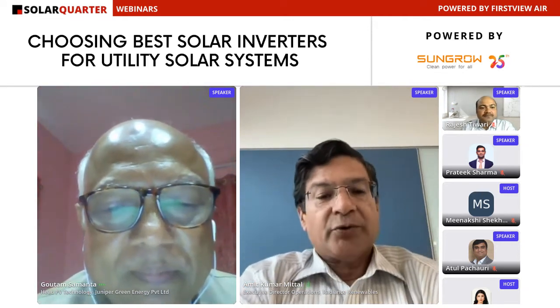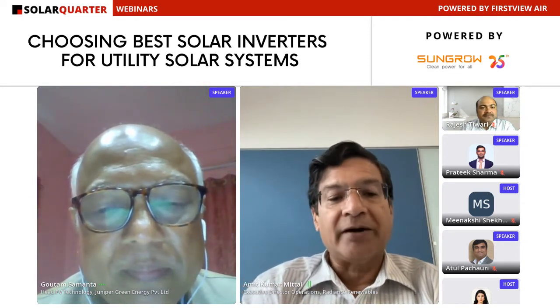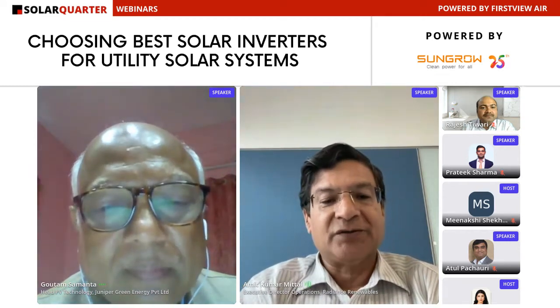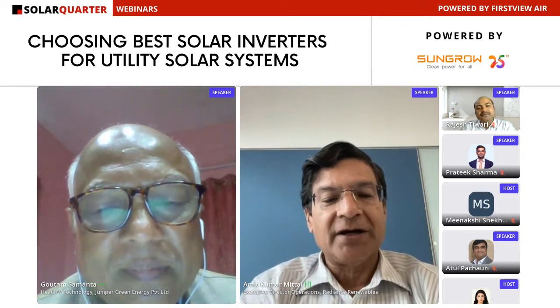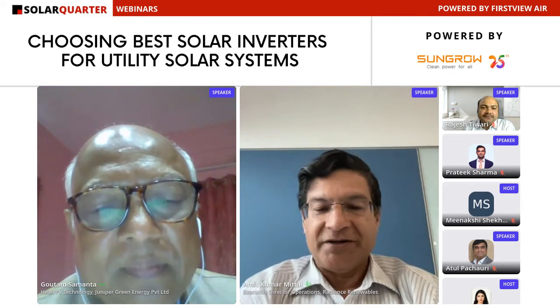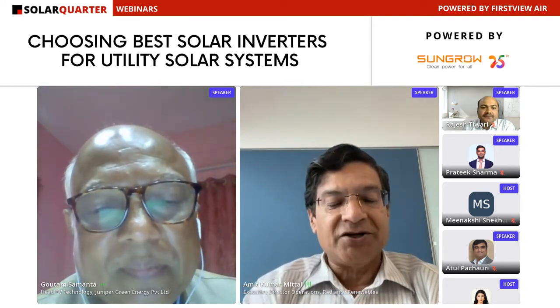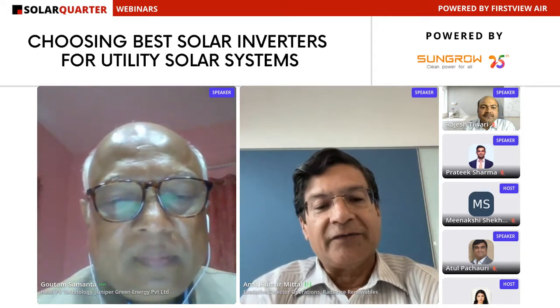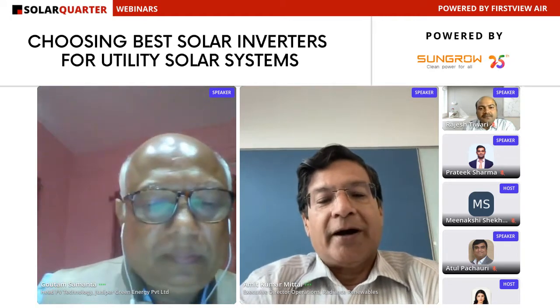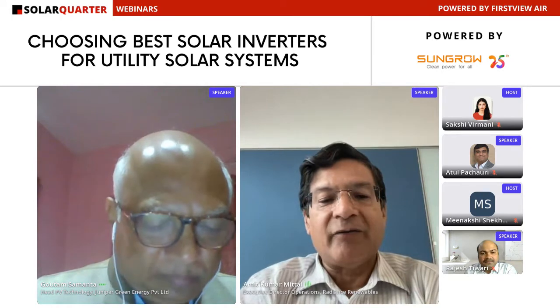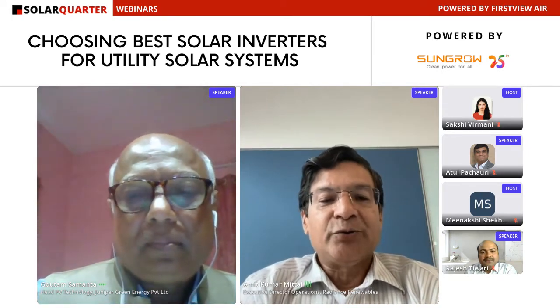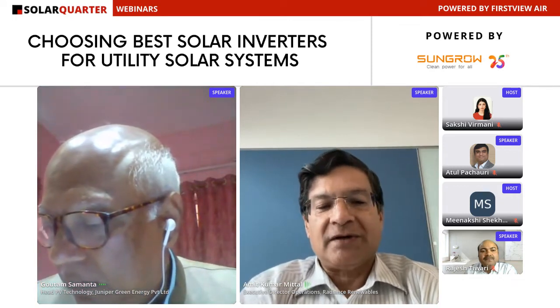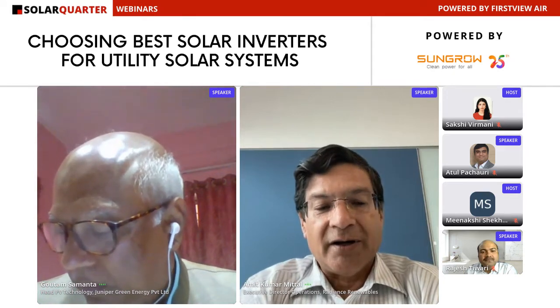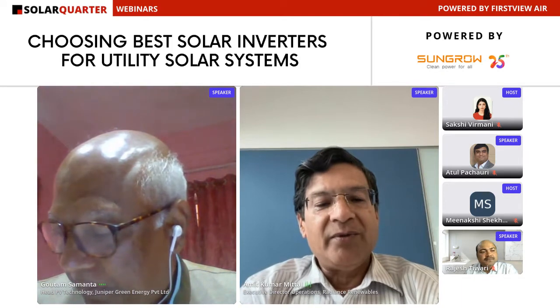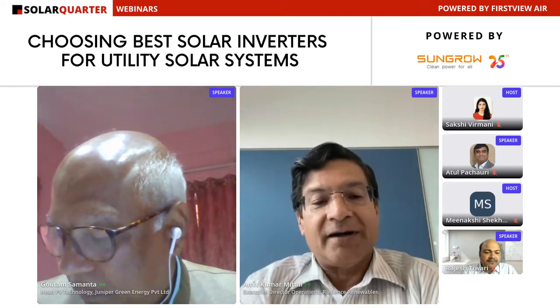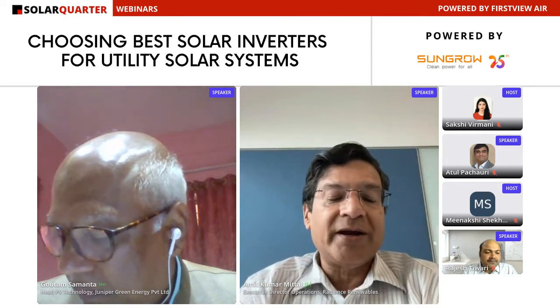Yeah, I think you have touched upon a very important point, because typically, to improve the overall plant efficiency, the overloading has gone right up to 50%. Typically a 1.5 DC/AC ratio for fixed tilt, and even with the tracker, around 1.35 to 1.4 DC/AC ratio is quite common. So what happens during the peak generation in the daytime, at least a couple of hours in the case of fixed tilt and a few hours with the tracker, is that you have to limit the power, because whatever the AC capacity of the inverter is, due to the grid limitation you are not supposed to inject more than that. As an example, if my plant is 100 megawatt, because of the high DC/AC ratio I may be able to produce 105 to 110 megawatt, but the grid will not allow me, so I have to curtail my inverter to 100 megawatt only.